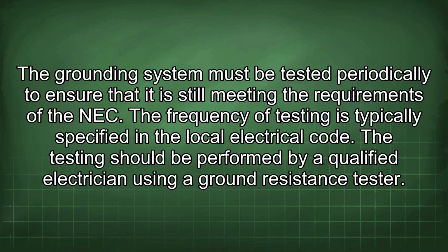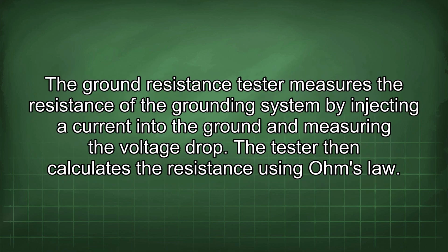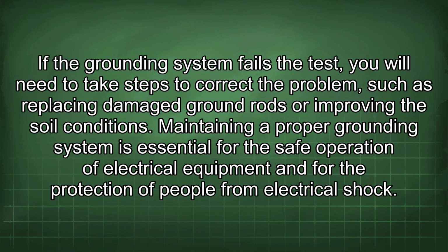The grounding system must be tested periodically to ensure that it is still meeting the requirements of the NEC. The frequency of testing is typically specified in the local electrical code. The testing should be performed by a qualified electrician using a ground resistance tester. The ground resistance tester measures the resistance of the grounding system by injecting a current into the ground and measuring the voltage drop. The tester then calculates the resistance using Ohm's law. If the grounding system fails the test, you will need to take steps to correct the problem, such as replacing damaged ground rods or improving the soil conditions.